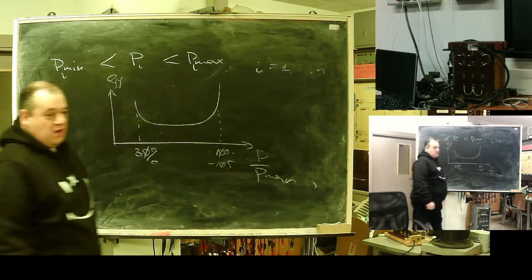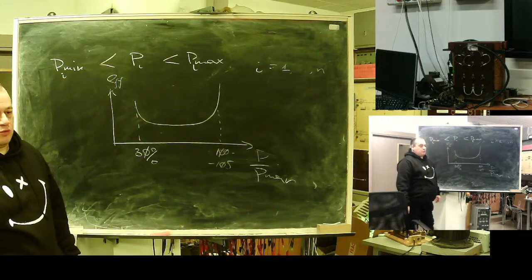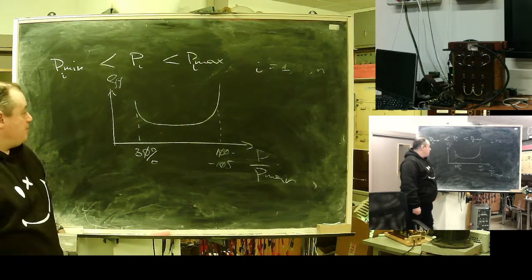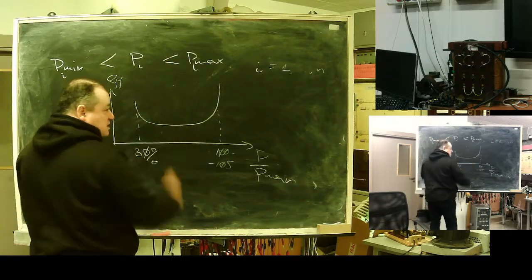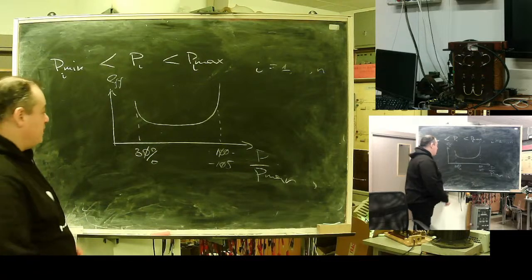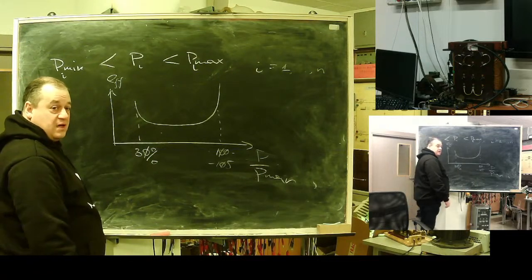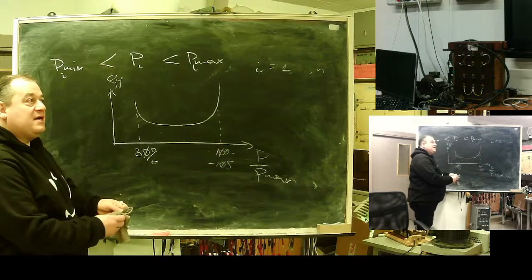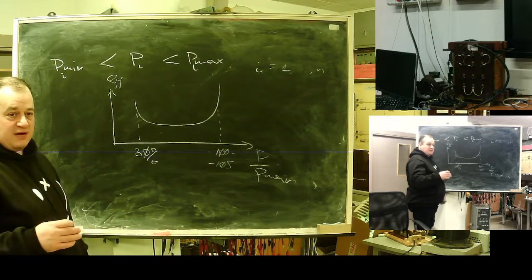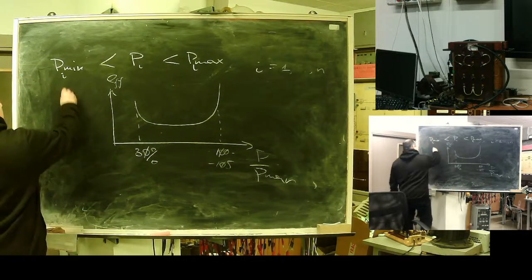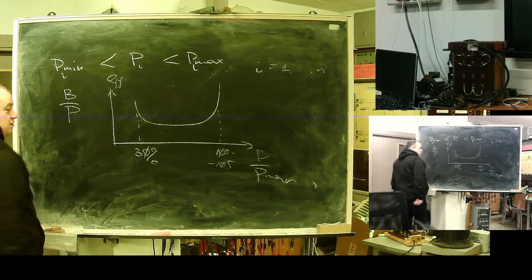At 105%, boost regimes are extremely inefficient, with 2 times higher fuel consumption. So this is an efficiency chart you will see. Professor, is it the fuel efficiency or the generator efficiency? Yeah, it's the fuel efficiency, the amount of fuel per 1 megawatt.